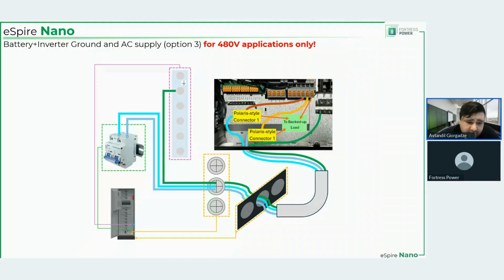But as I said, all of these 3 options where we utilize the breaker, which is on the right side of the battery unit, this is for 480 volt applications only, because this breaker is receiving 277 volts and converting that to approximately 220 volts for the AC circuits inside. If you have 208 volts, you cannot deliver that to the transformer because the output voltage on the other side will be too low and also might throw an error on the transformer. And it's not the way to do it.